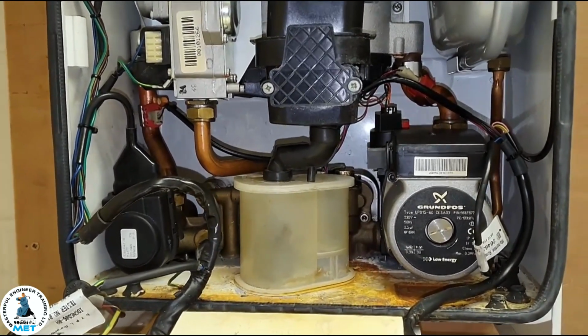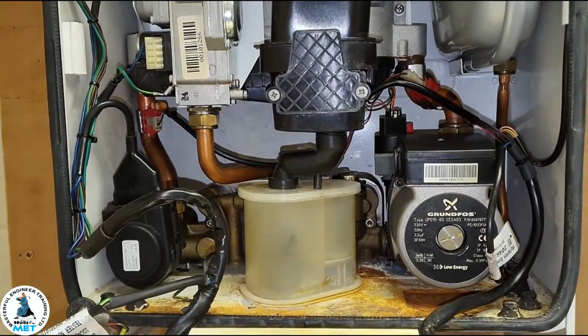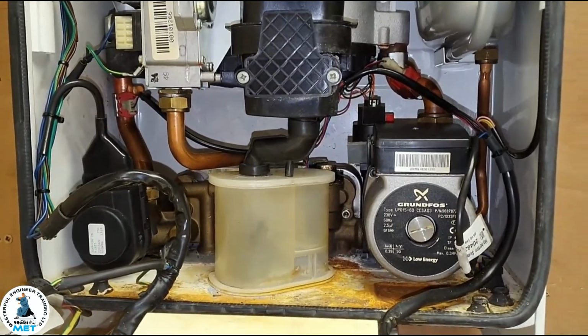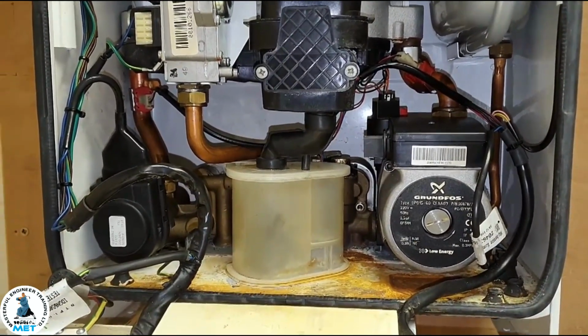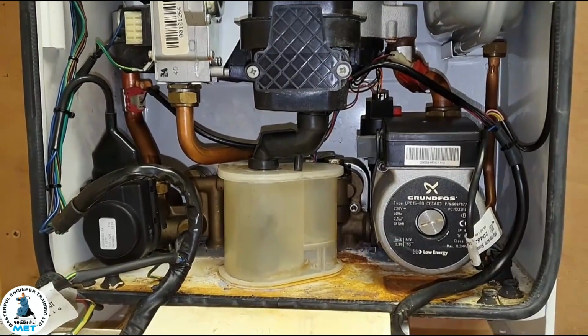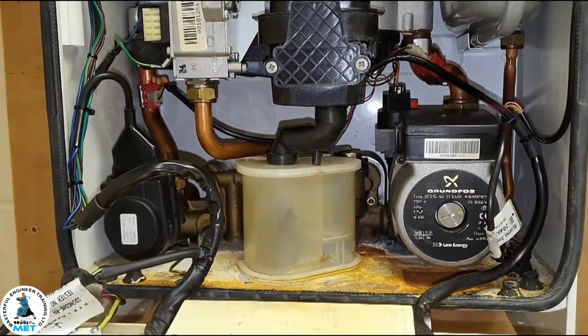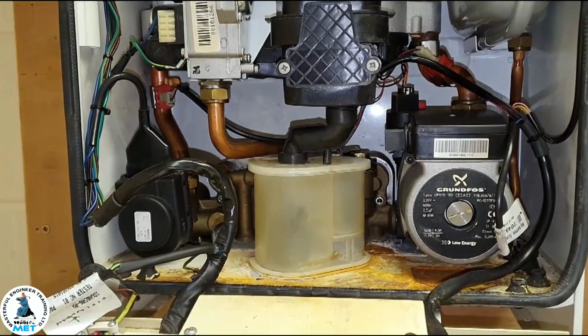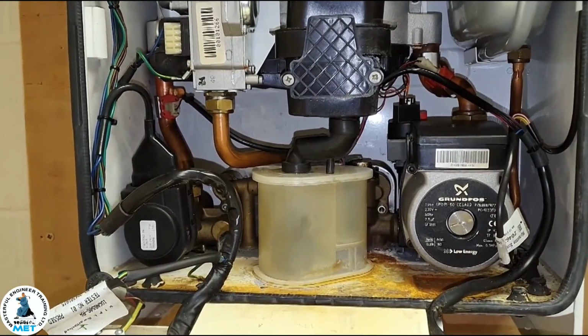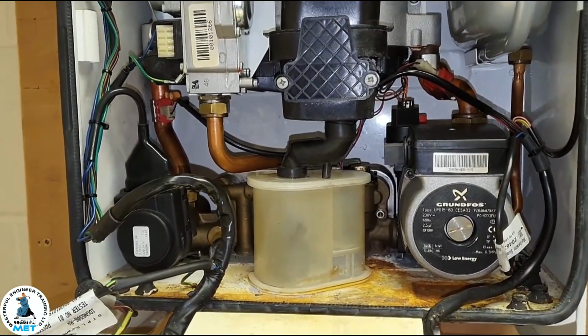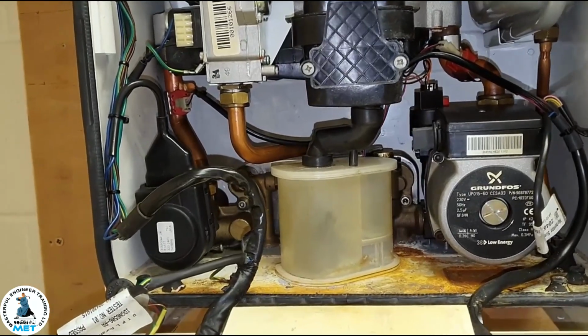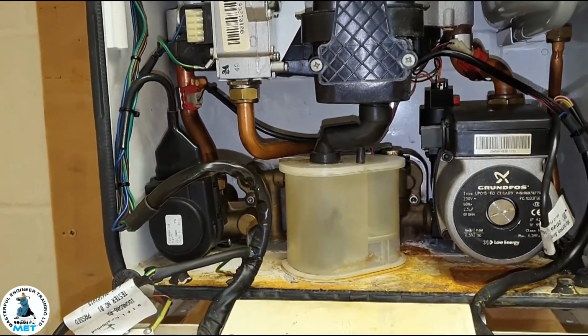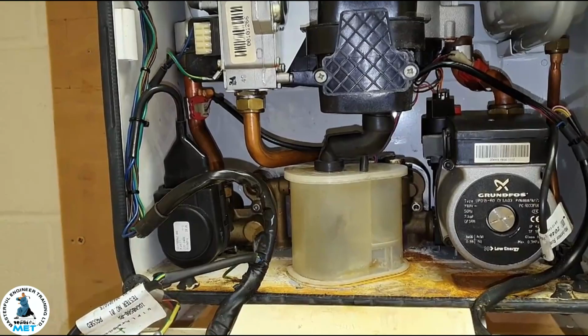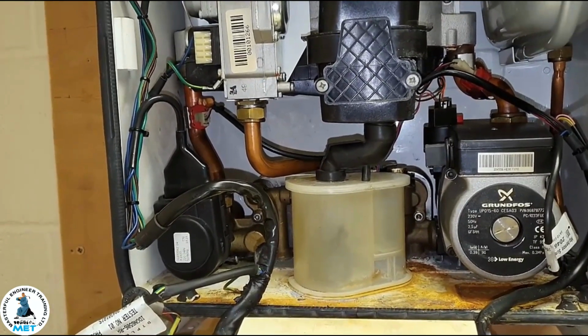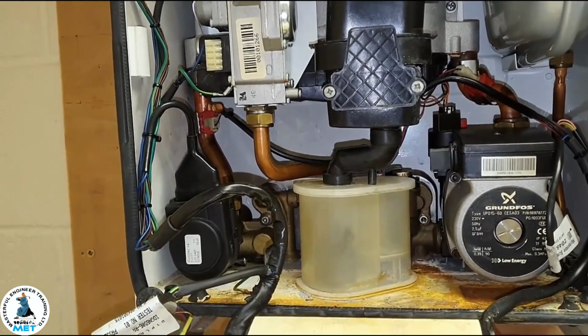Well that's it, so you can look at that. What I would do then is drain the boiler down to 1, and then monitor it. Give it maybe 20 minutes, half an hour, and see if the pressure starts creeping back up. If it creeps back up after that time, you can also listen, because sometimes if it is passing, you can actually hear the water hissing slightly.